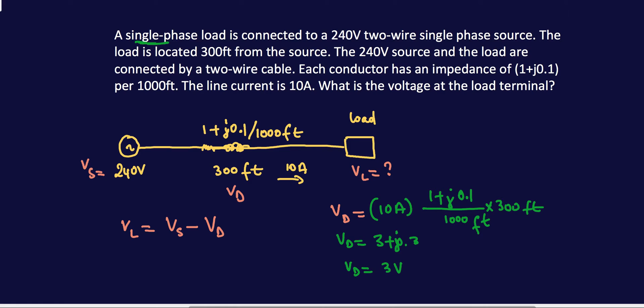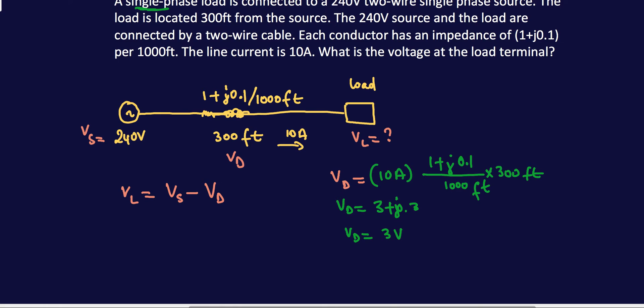So the current will actually flow through the neutral as well. It's not like a three-phase system. The neutral return current is equal to the phase current, so you have to take into account the return path. The voltage drop through the complete path is going to be whatever you have here times two, because you have to take into account for a single phase. The current flows through the neutral at the same time.